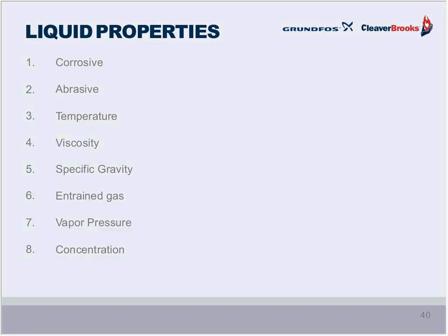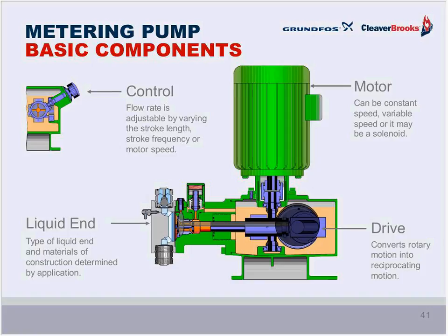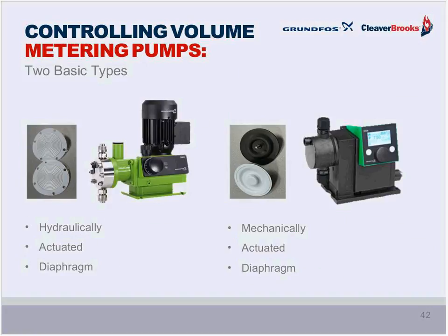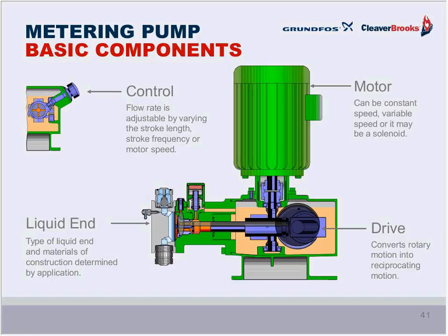Since a variety of liquid properties can be encountered when injecting, there are strategies for dealing with all these properties. In general, these are the liquid characteristics that must be considered when selecting a dosing pump for applications. Part of a chemical feed system is the metering pump. All of these have 4 basic components. They are the motor, which can be constant speed, variable speed, or even a solenoid. Then the drive assembly, which converts the rotary motion into reciprocating motion, unless a solenoid is used. And the liquid end. The liquid end is where the liquid comes through. Inside of this are the moving parts that do the actual pumping, so it's the diaphragm, which we'll see in a second. Finally, we have the control adjustment, which is adjustable by varying the stroke length, the stroke frequency, or the motor speed.